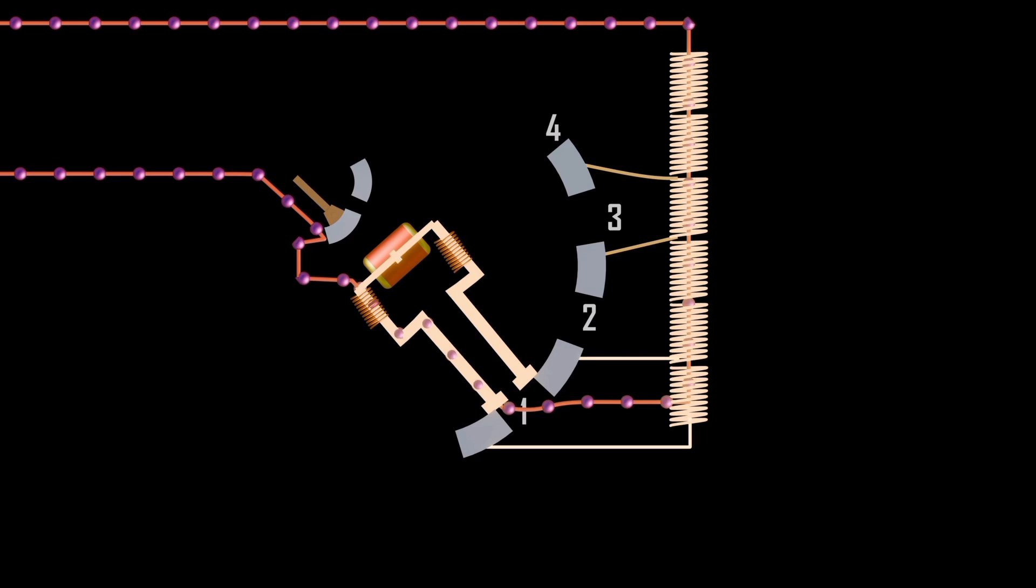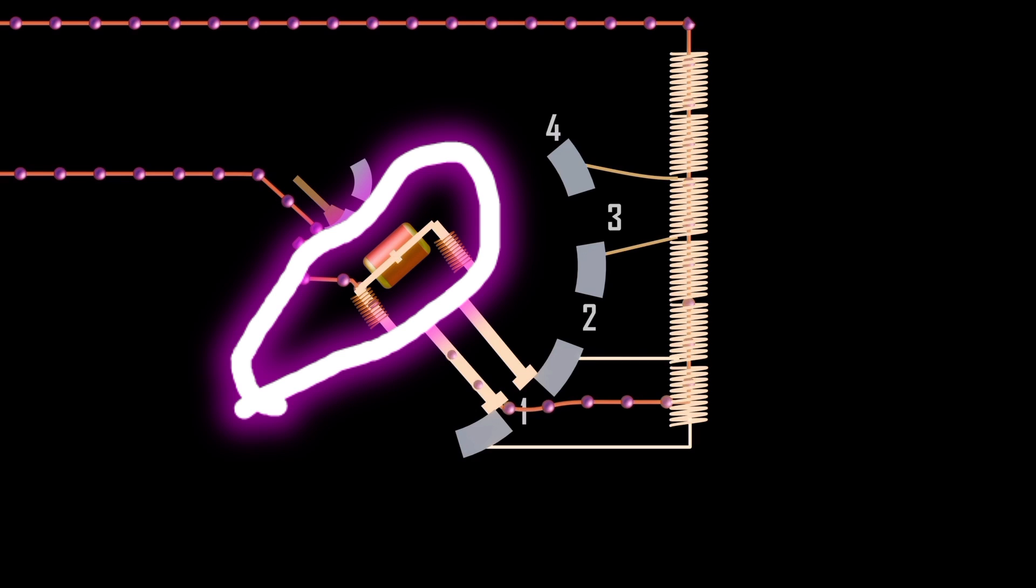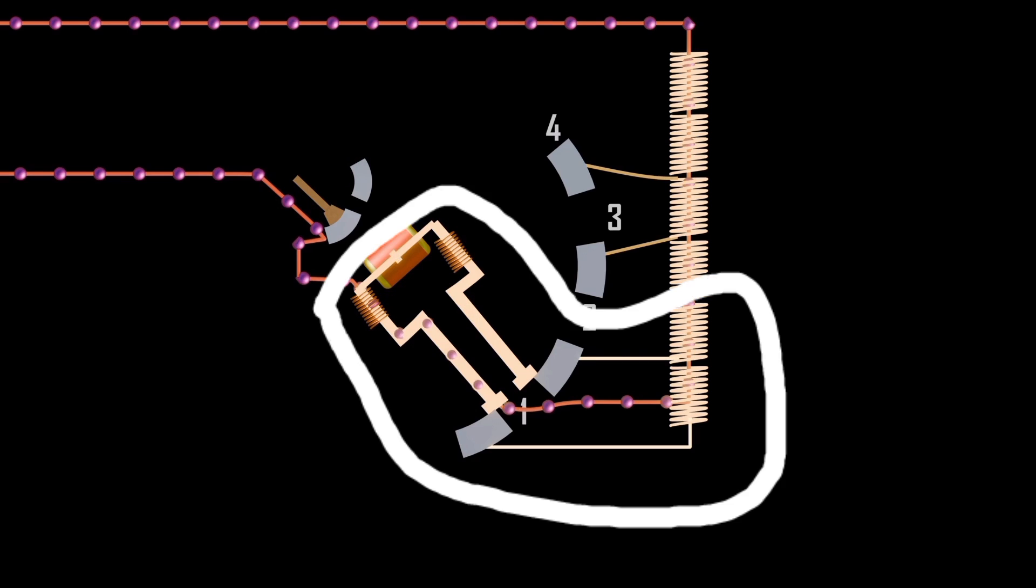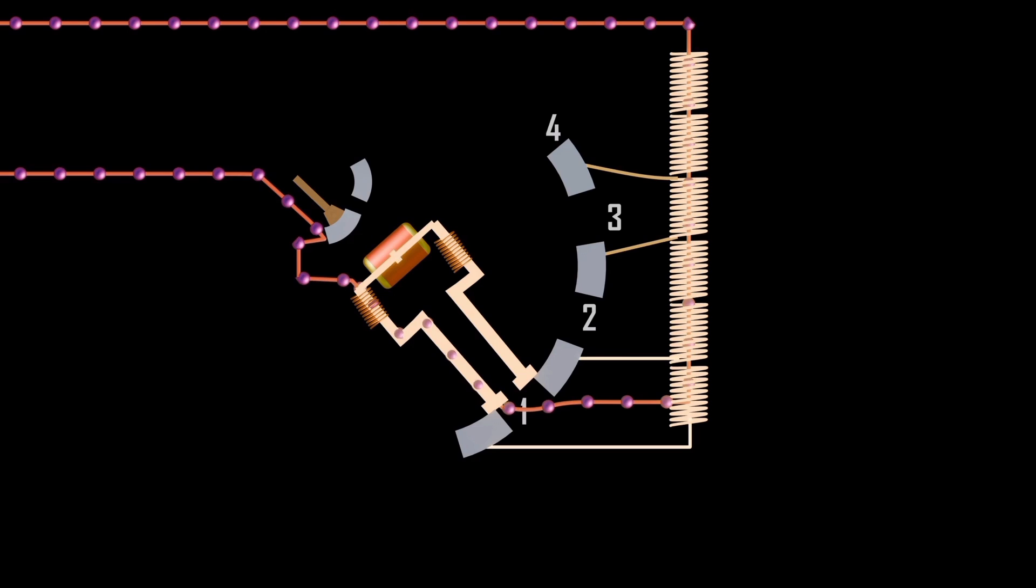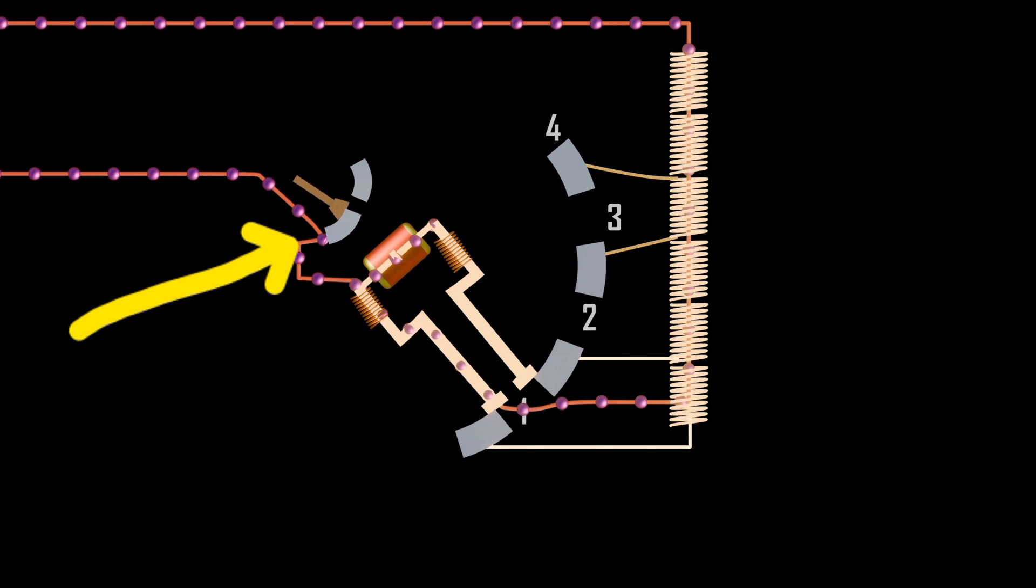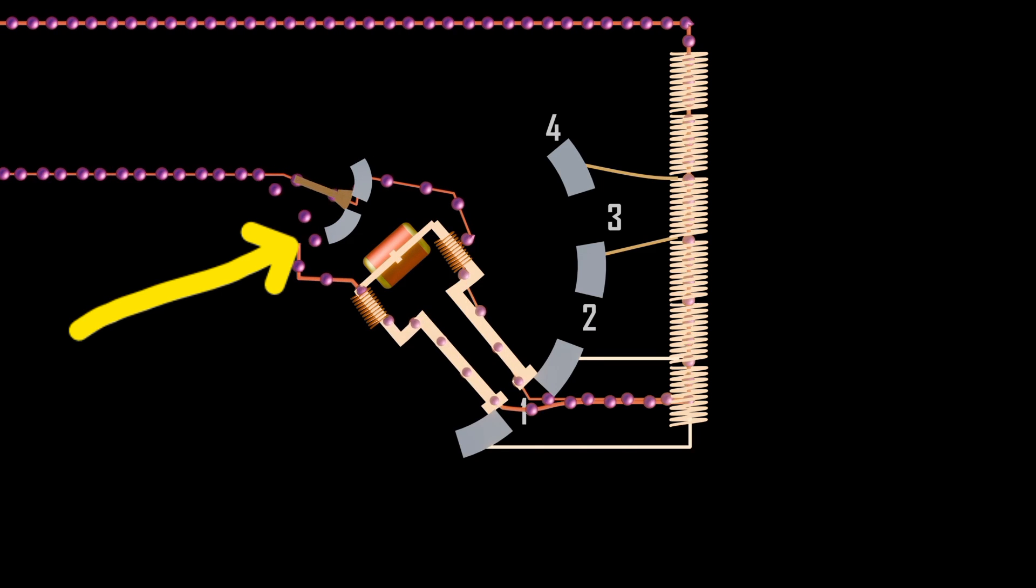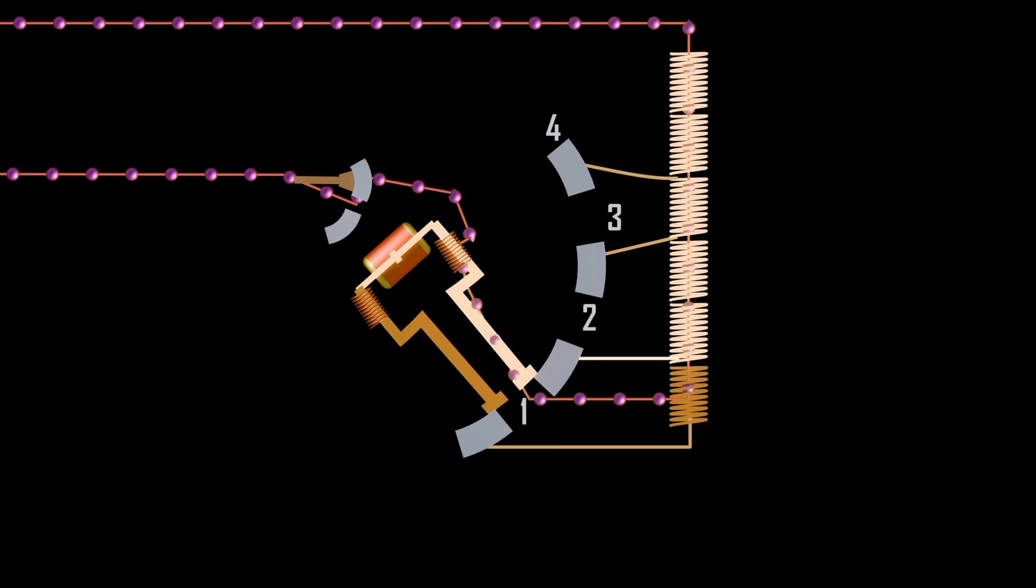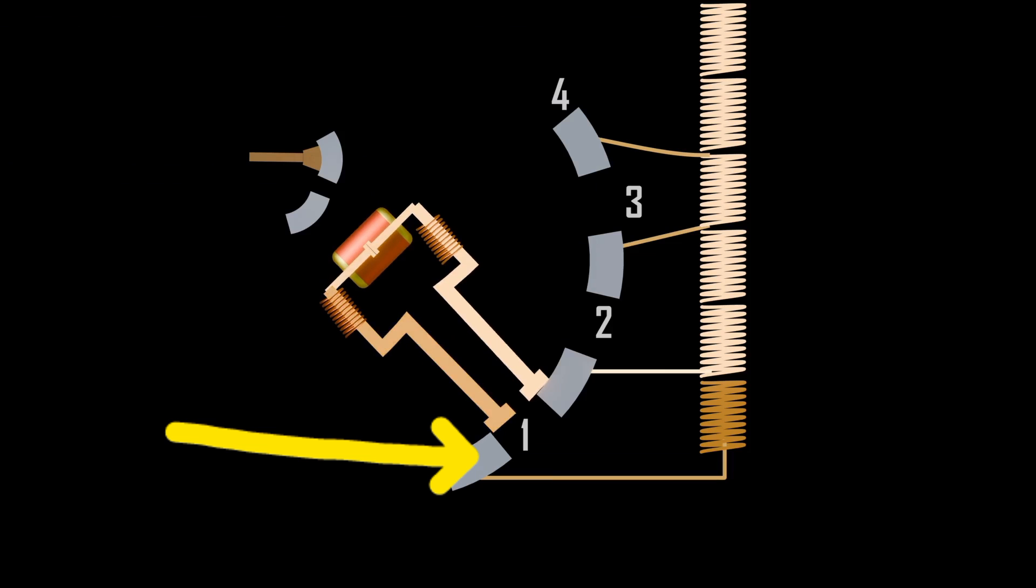Now we close the vacuum switch, therefore forming a loop between coil one, coil two, selector contacts and vacuum switch. Now since the vacuum switch is closed, we can safely turn the bypass switch to the other contact, energizing the other side of the selector switch. Now we can turn the selector switch to tap two, and then open the vacuum switch.